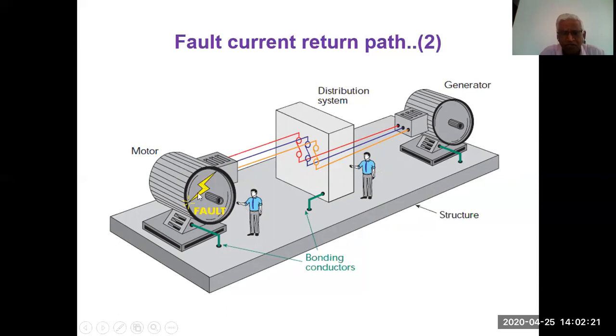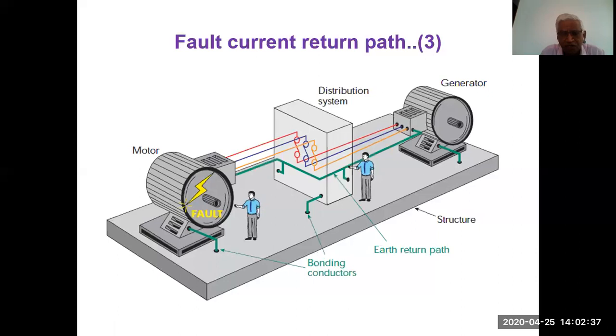The moment there is a fault, the current comes through one of the phases and returns back through this. So his body as well as his hand are at the same potential, so there is zero potential difference between them, and it will not give a shock. Take a third case. In this case, I have provided both. I have provided the green wire as a ground wire, and the phase is still remaining.